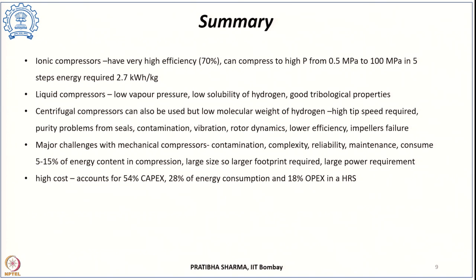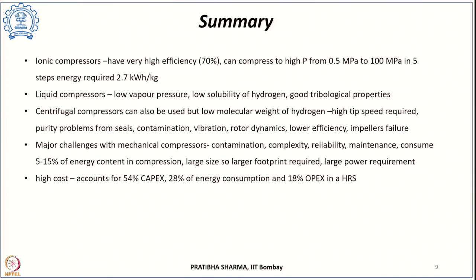Another option is a centrifugal compressor, but the major problem is the very low molecular weight of hydrogen. To compress hydrogen to an appreciable pressure, a very high tip speed is required, leading to contamination from seals, vibrations from high tip speed, problems with rotor dynamics, very poor efficiency, and potential impeller failures. As such, volumetric type compressors are preferred over centrifugal type compressors for hydrogen compression among mechanical compressors.